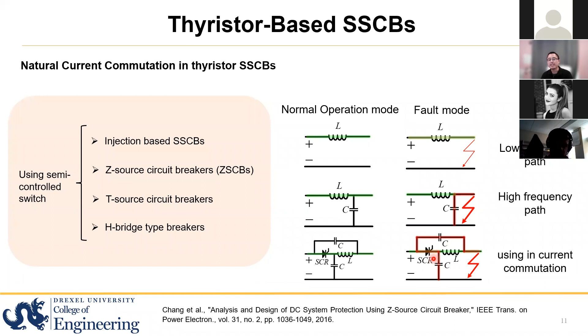Then I want to emphasize that this Z-source-based circuit breaker has an automatic protection function, because it does not need any detection of the fault. It does not need any control to get involved. As long as you have a fault and the fault impedance is low enough, then this capacitor will discharge and the thyristor will be automatically turned off. And based on this characteristic, a lot of Z-source-based circuit breakers have already been proposed, like the cross Z-source, which is like a cross structure, the parallel one, and also the series one, based on different configurations of the topology. But for any of them, the working principle is very similar. When we have a fault, this fault will automatically generate a reverse current flowing through the thyristor and turn off this thyristor.